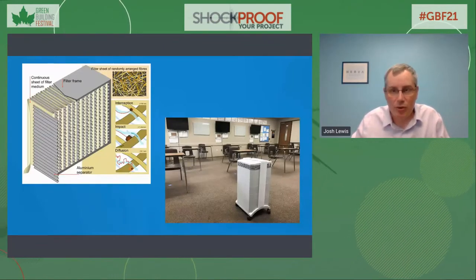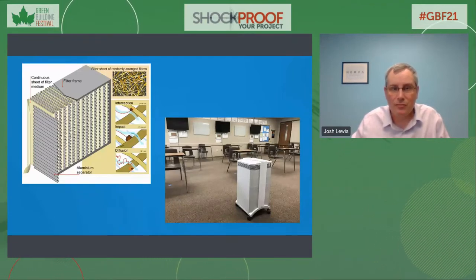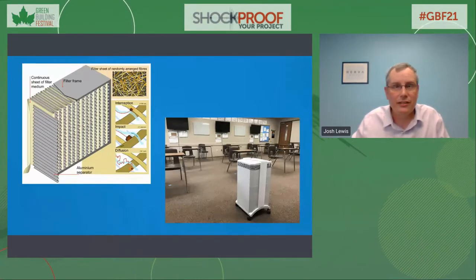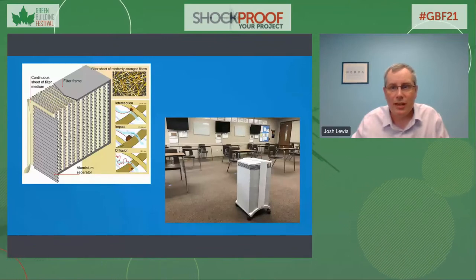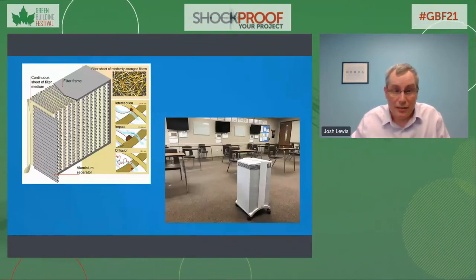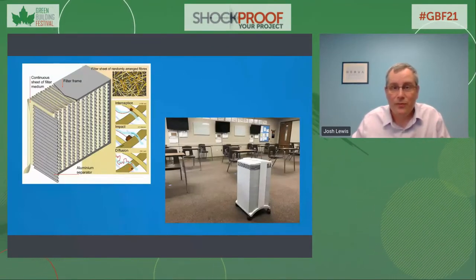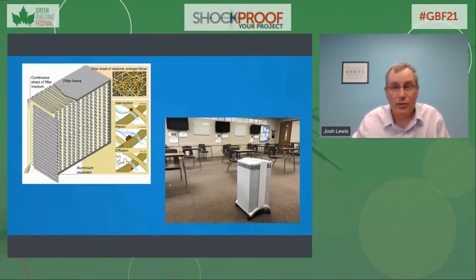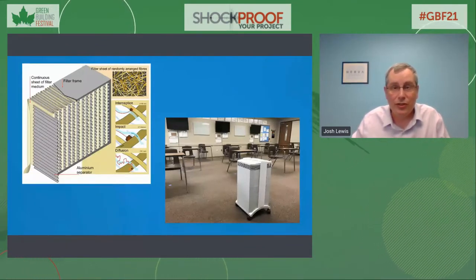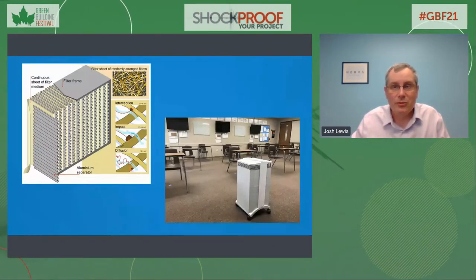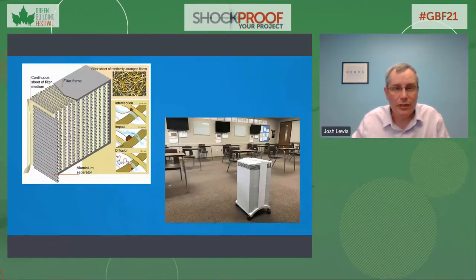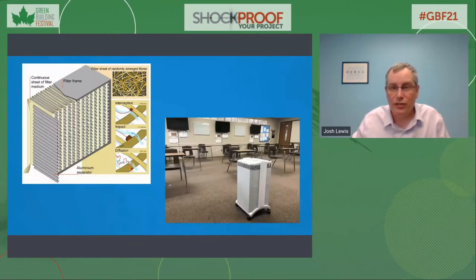They are definitely more effective at trapping contaminants, but due to their inherent tightness, the differential pressure drop across a HEPA filter is quite high, even when they're new. Therefore, most HVAC equipment cannot accept HEPA filters, as they were not designed for it, and if installed, they would cause an unacceptable decrease in system airflow while simultaneously increasing fan electricity usage by a significant percentage.